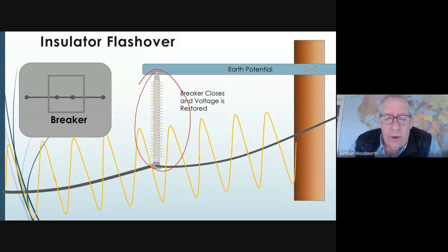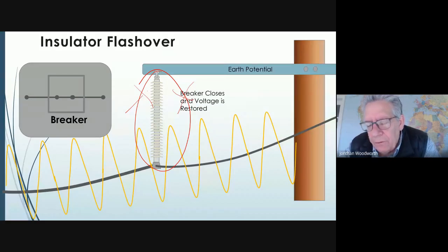And this has nothing to do with arresters per se, but what we would like to do oftentimes is make sure that never happens, that we never have this sequence. So our goal is to reduce the number of outages, because now we just experienced what's called a momentary outage, but to the eye, it's a blink. Oftentimes you'll see during a thunderstorm, there'll just be a blink of the lights. That blink meant that lightning struck the line somewhere and caused a breaker to operate, and then the breaker brought the lights back on. But it's all done so fast, you really don't see it.